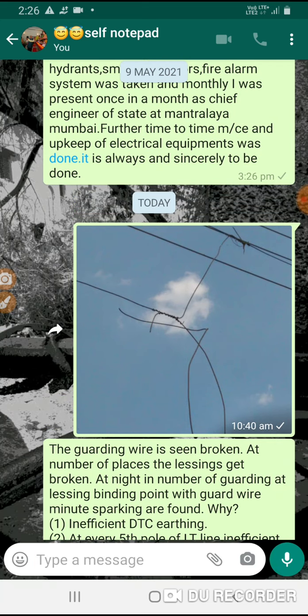This is a joint. This is a joint. And at this joint, generally, due to imbalanced load on the transformer, the neutral always carries unbalanced current. And as the DTC earthing is inefficient, it carries floating voltage. That floating voltage is carried by the pole, and on that pole the guarding is fixed, and that floating voltage is transferred to this guard wire. In this guard wire and its lacing at the joint, due to air gaps in the joint, there is small sparking seen at night, and due to this continuous sparking the lacing breaks.